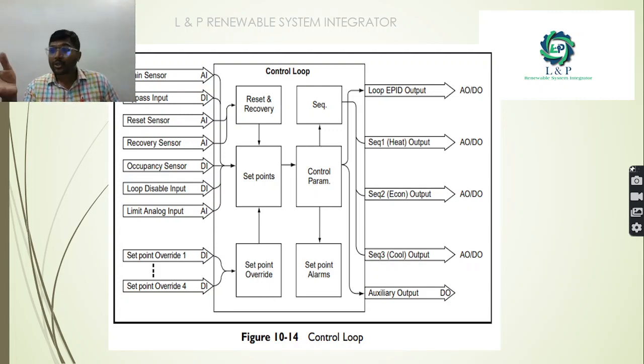So as a control output, as a control parameter, it can be a PID loop. We can produce an analog output, or in certain places you need only a digital output, and you can produce that too. So this is the entire concept of a control loop. We will have the set point, and based on the set points we have some control parameters and sequences. In certain places, if any issues occur, we also need to raise alarms.